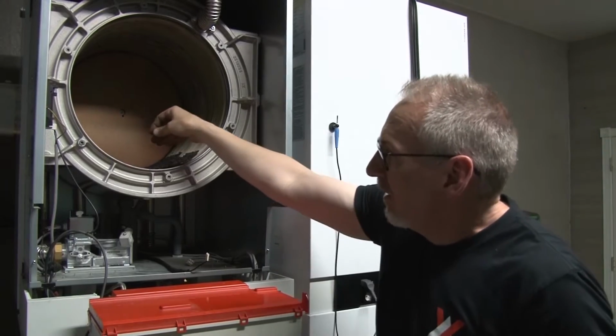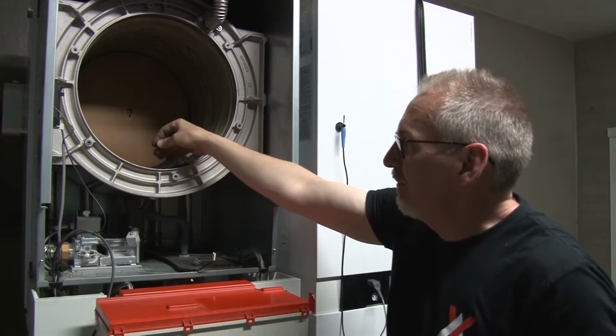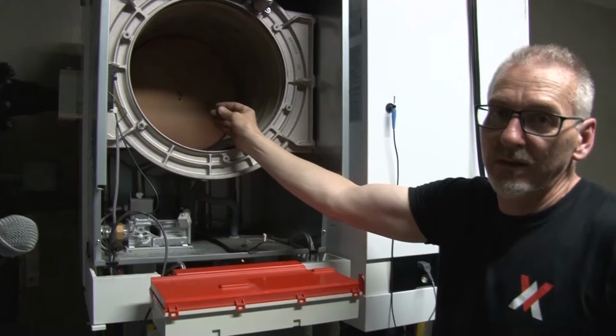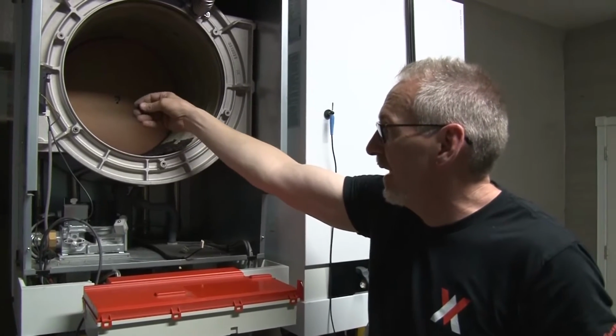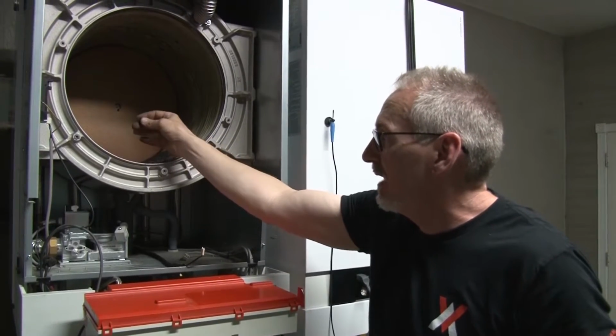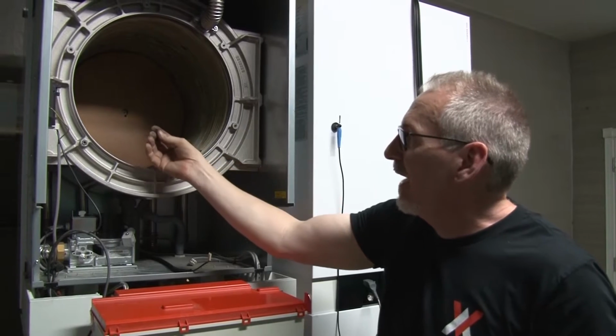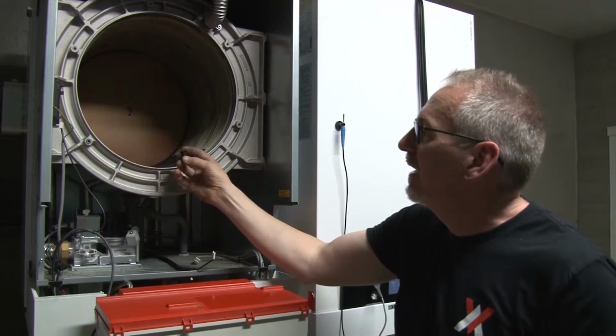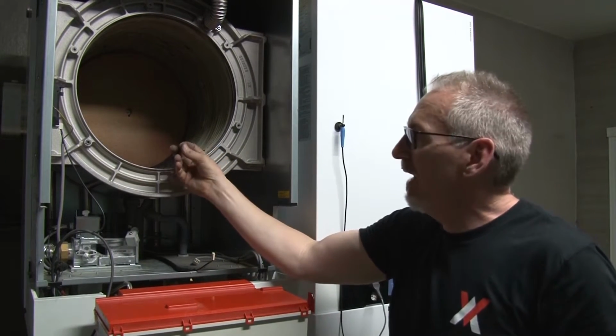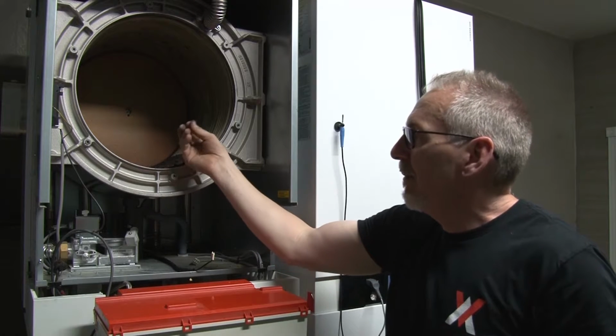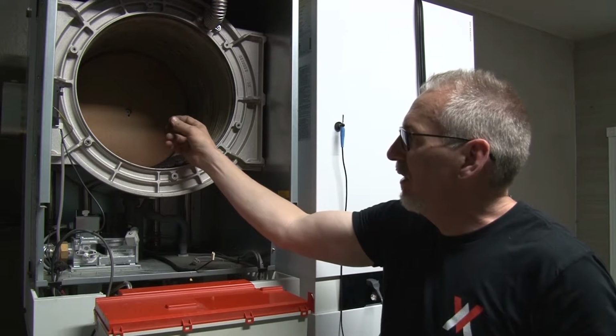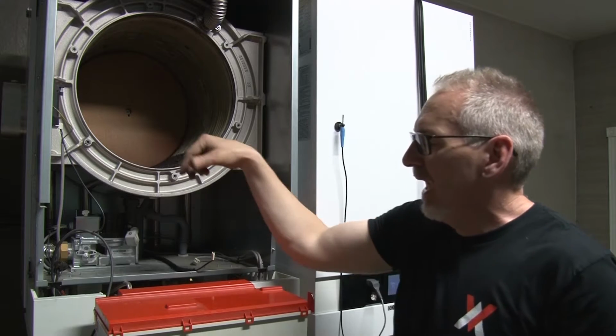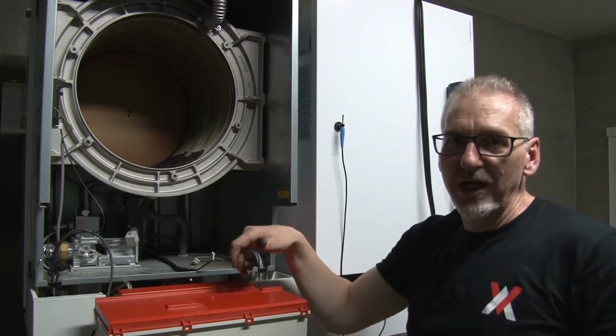What I like about this particular style of heat exchanger is that it needs maintenance, and Viessmann by no means is saying you never need to maintain your boilers. You need to maintain these. We recommend annual preventative maintenance, just like your car, right? You drive that car so many hours a year, and you have to change the oil after so many kilometers. These boilers have over 15,000 hours of operation time on them.